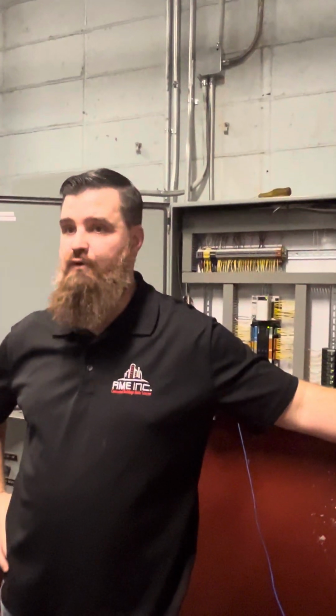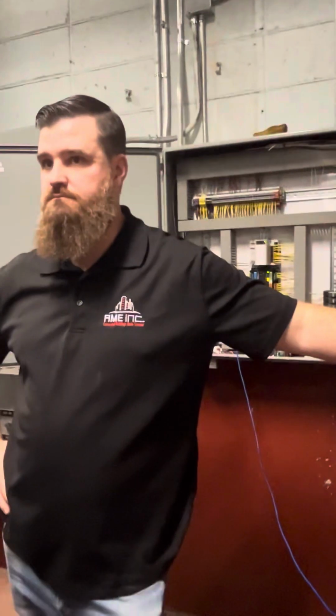So we could put in a lockout for that - we shouldn't be able to use both of them simultaneously. Right, that's what I'm saying. Because if this happens to go on for some reason, none of those should be operational at all. It's supposed to be locked out, and the fan's supposed to go to 100%. And if any of those units are on - 1, 2, or 3 - it goes 1/3, 2/3, 100%. So it's not a hard modification, but it's going to take a little time.